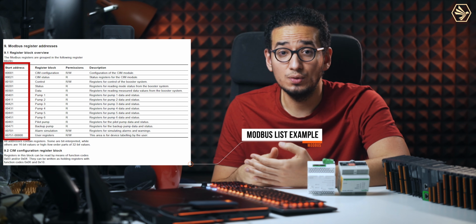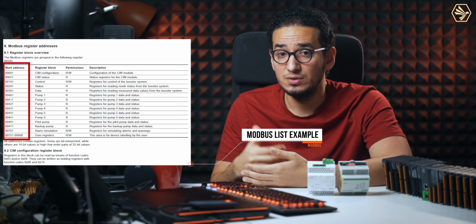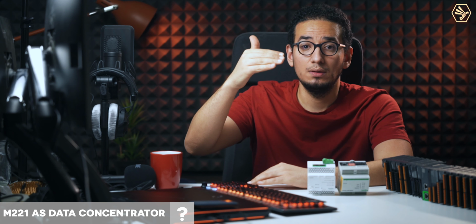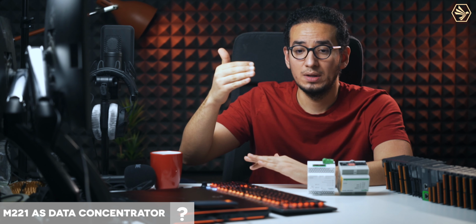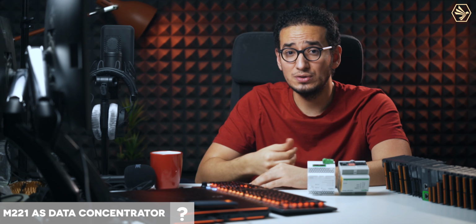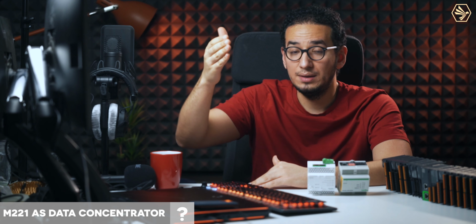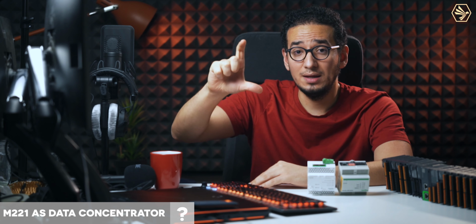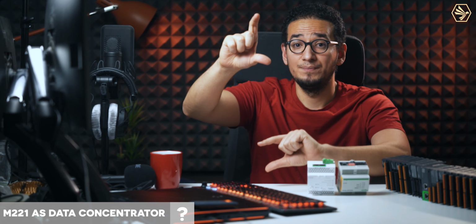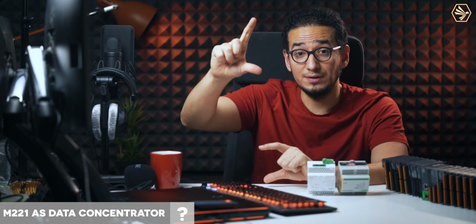Sometimes I'm using this PLC as a data concentrator, because if you browse the integration document or any Modbus list for connection with OEM panels or whatever, or even power meters, generators, you will find there are gaps between the memory areas. Like, for example, I have the address 40,001, and I will not consider the function codes, which is the 4. So you have address 1 and then address 5. I need the data between 1 and 5, and then I need the data between 145 and 150.